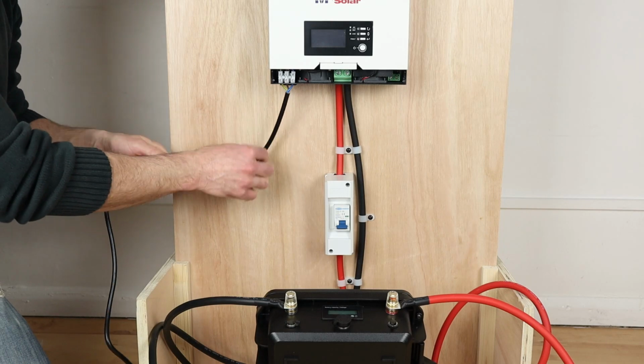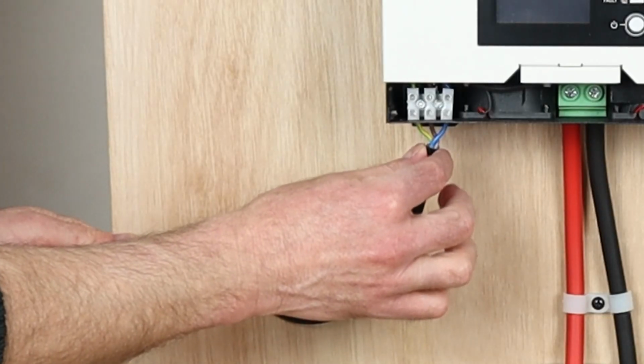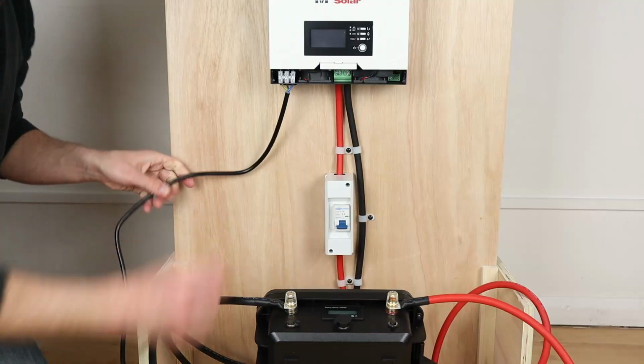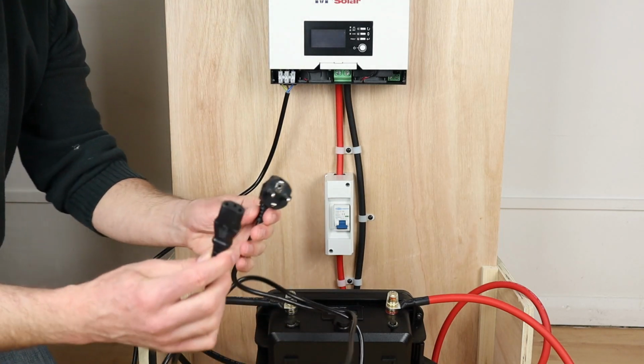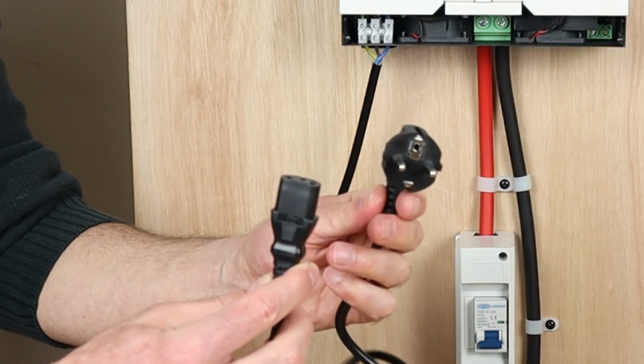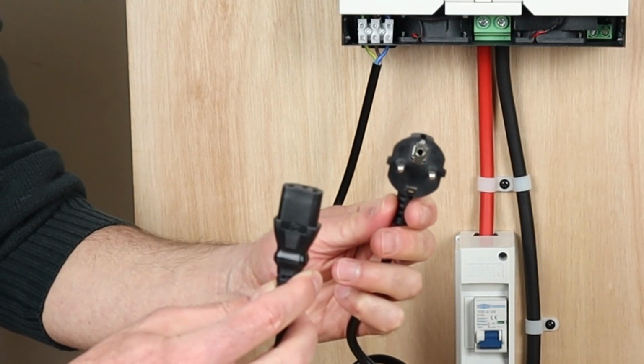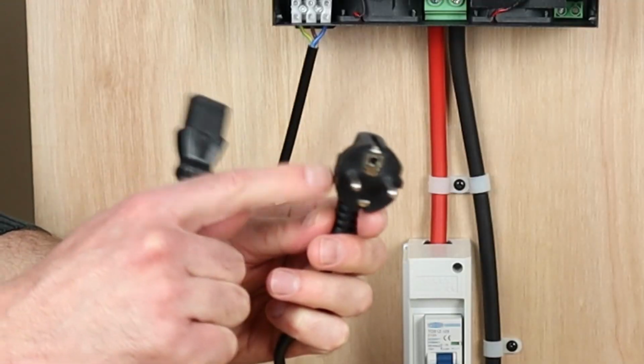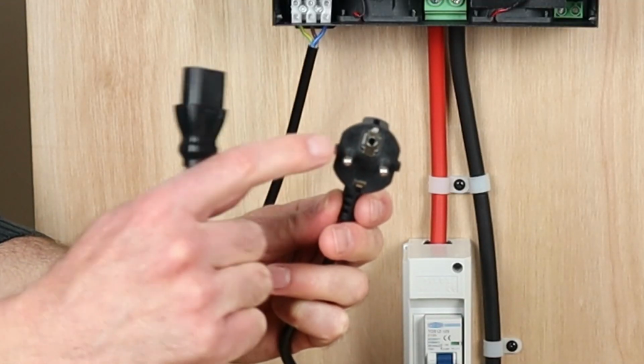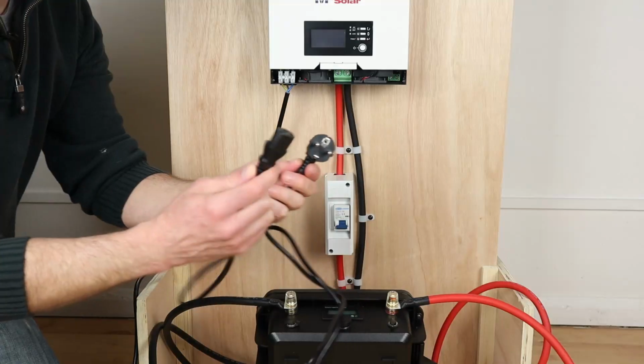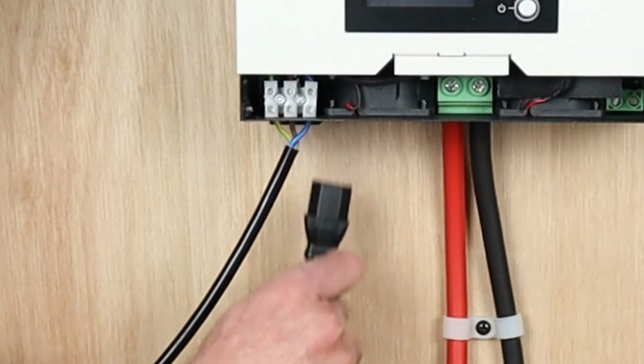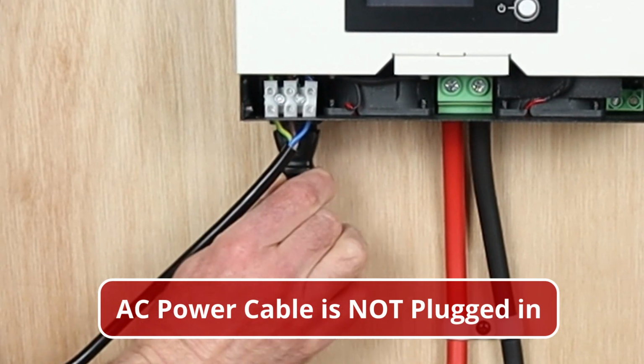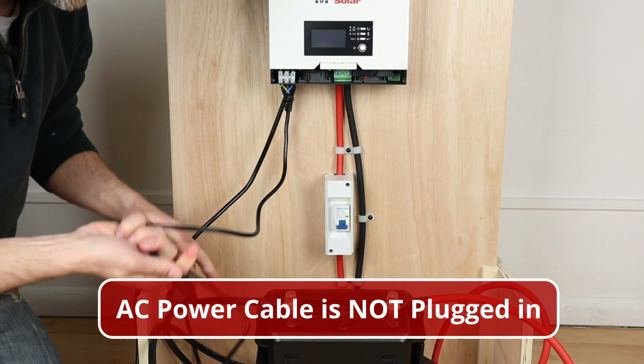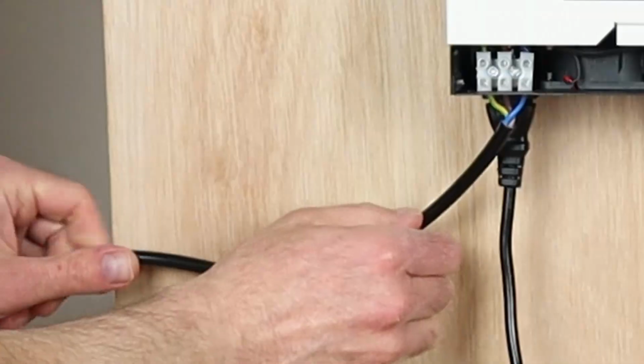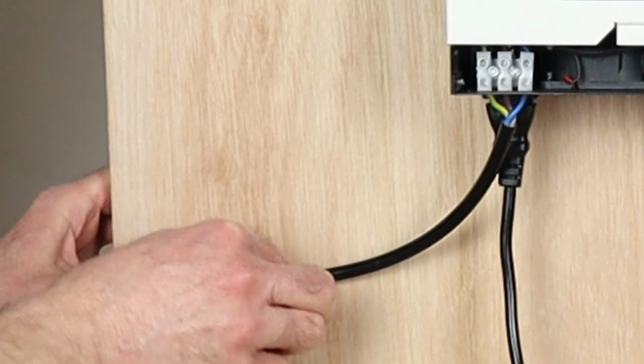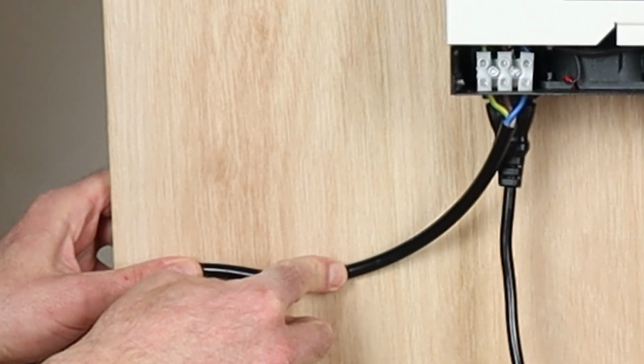So in order to secure this cable I've just added, to ensure there's no tension and it doesn't pull out from the terminals, I've picked up the AC input cable - this is what you use to hook up to your mains outlet if you want to use utility power. I'll show you a different cable with a standard 3-pin plug later in the video. What I'm going to do now is plug this in to check it doesn't interfere with it. So that's plugged into the AC input now, which enables me to go ahead and put this on the backboard and secure it properly.